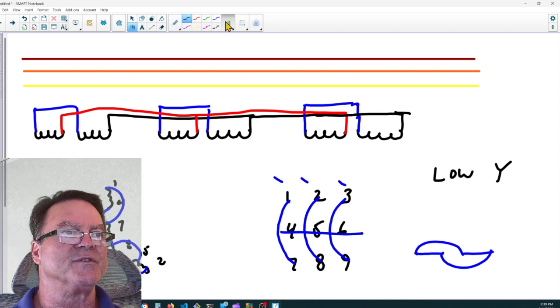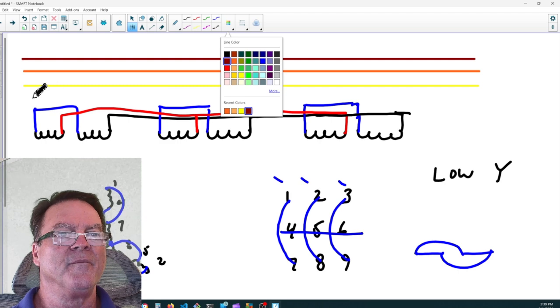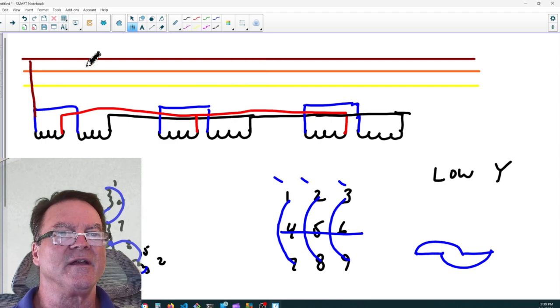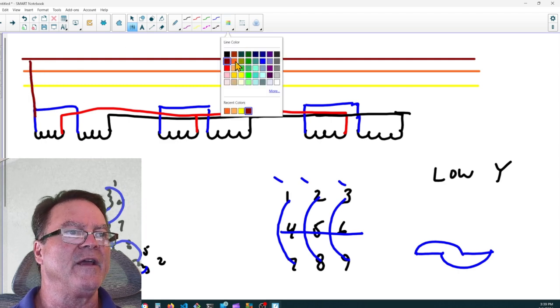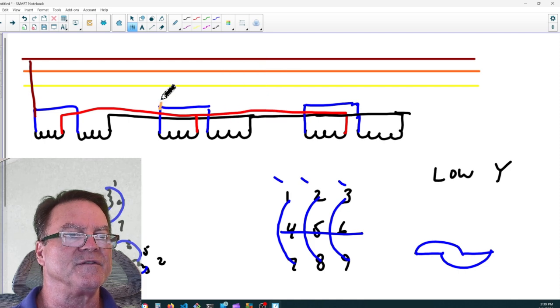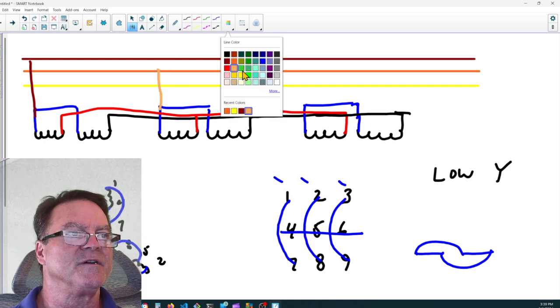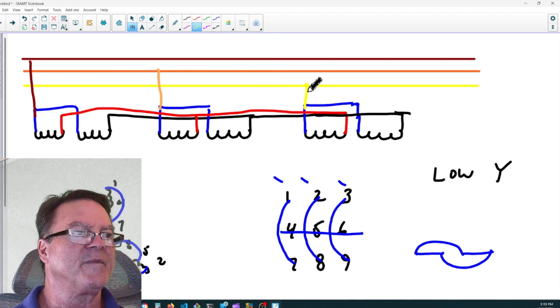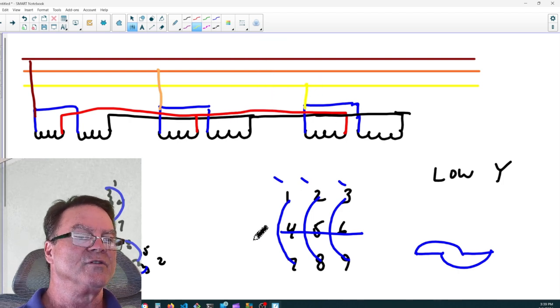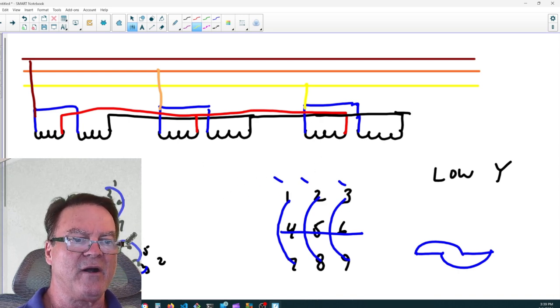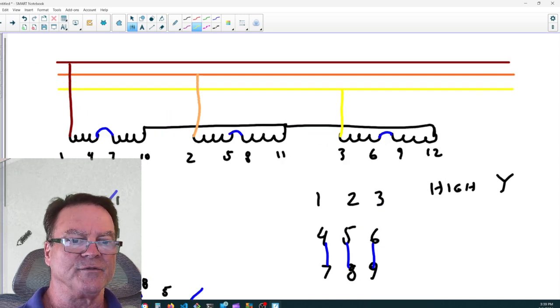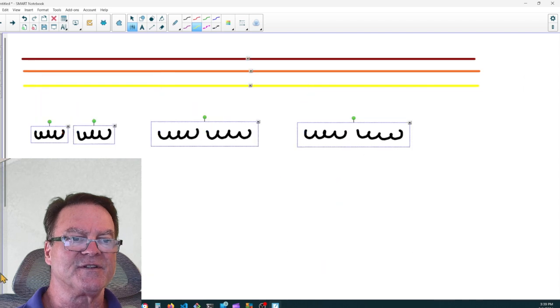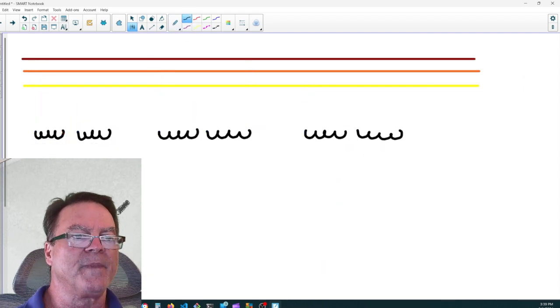And then we're going to use 1, 2, and 3 as our power out. We'll go to A phase, B phase, and C phase. There. So that's how we connect low voltage and high voltage for Y. Remember, you put them in parallel for low voltage, you put them in series for high voltage. Delta is the same story.